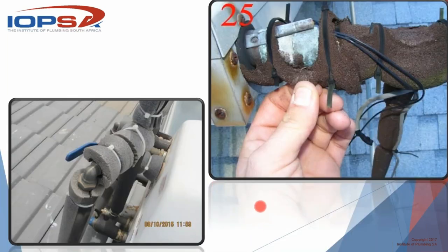Some more examples of badly installed lagging. This type of lagging with a ziplock on the end is never ever going to be R1. So never, no matter how well you install it, it's not going to comply. This has been attacked by UV over a number of months and years. You can see clearly that's what it does. And this is exactly what we try and prevent when we say we want to protect it, because this is now completely disintegrated and it's not doing anything at all.